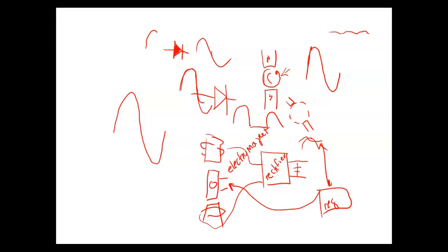Over here on our AC generator, though, we are using a permanent magnet. So all we're doing is spinning a permanent magnet, north-south, and then up here we have our coils. Because on a AC generator, we don't want to change the strength of the field. We want it to be controlled by the speed of the motion. So these things are going to last a lot longer. We don't have that commutator back there we have to worry about. What happens is these brushes are made out of carbon, and of course they wear down as they're running against something that's in motion. Eventually the brushes will wear out, and then of course your AC generator wouldn't be any good.